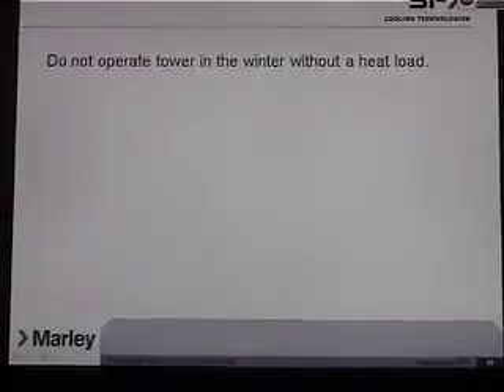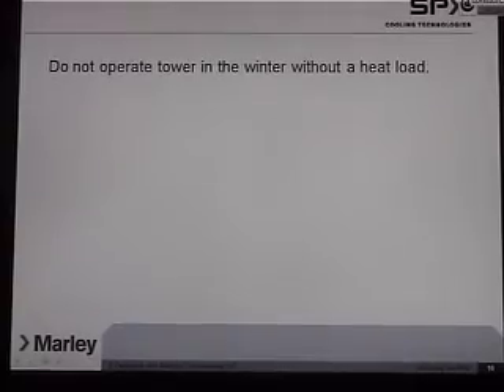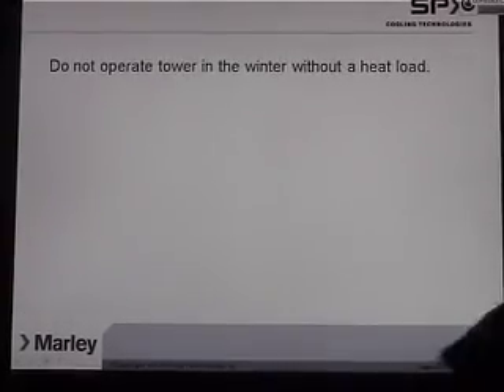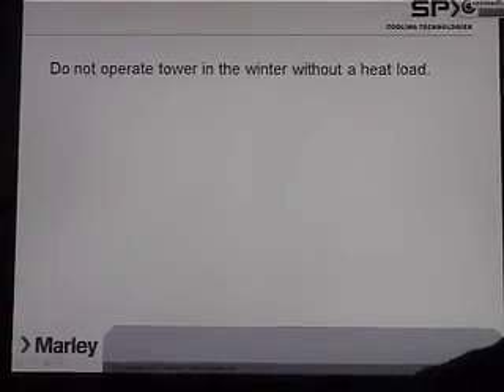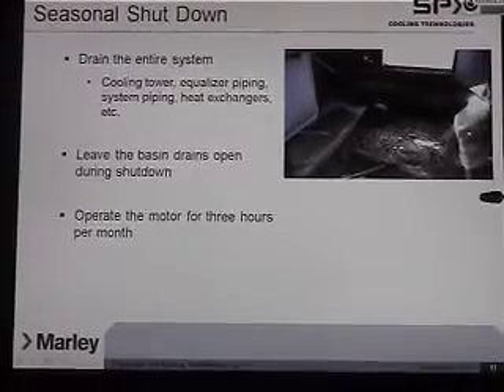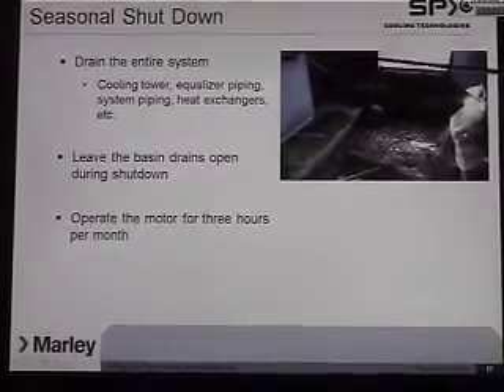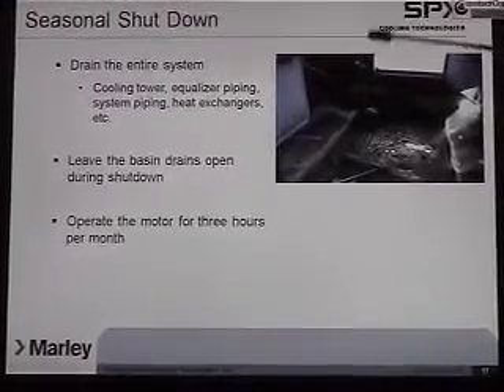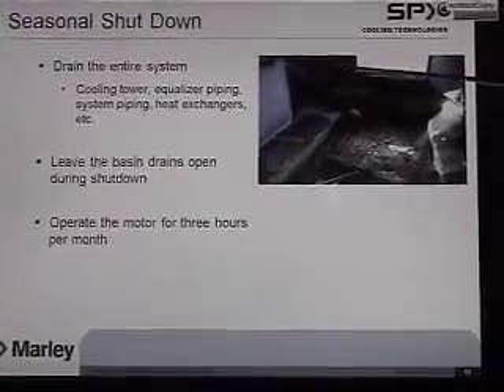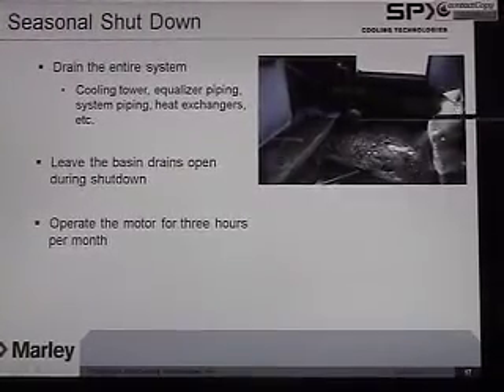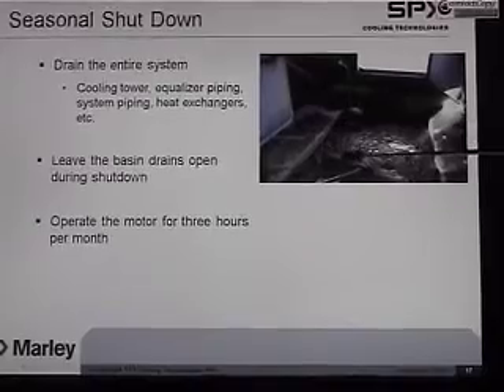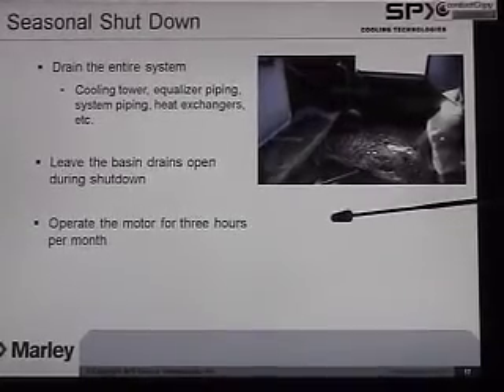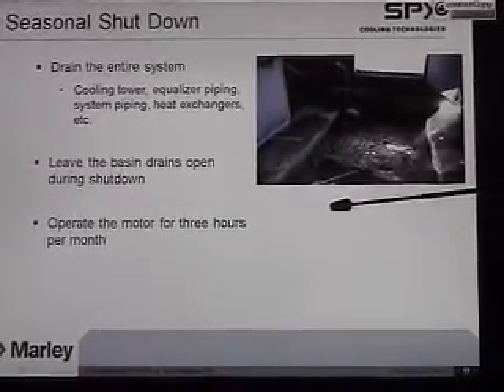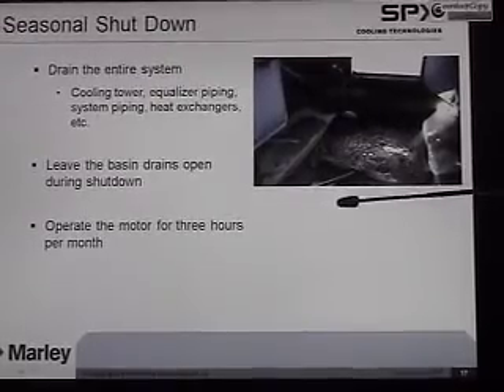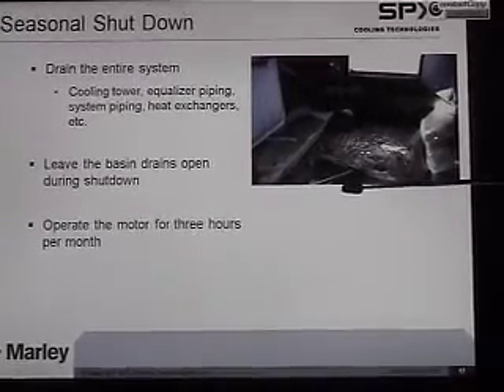And don't operate your cooling tower in the winter without a heat load, or you'll freeze. It'll make a big mess. Seasonal shutdown: it's recommended to drain the entire system. Leave the basin drains open, and the fan motor is required to be operated for 3 hours a month.